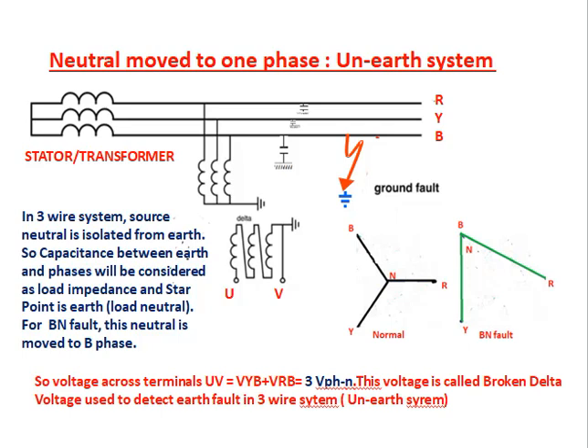In an unearthed system, the neutral moves to one phase. One side of the stator winding is shorted together but not connected to earth — the neutral is isolated. In a 3-wire system, capacitance between earth and each phase is considered as load impedance. For a BN fault, the neutral moves to the B phase. The voltage across terminal UV equals Vyb + Vrb = 3 times the phase-to-neutral voltage. This is called the broken delta voltage, used to detect earth faults in unearthed (3-wire) systems.